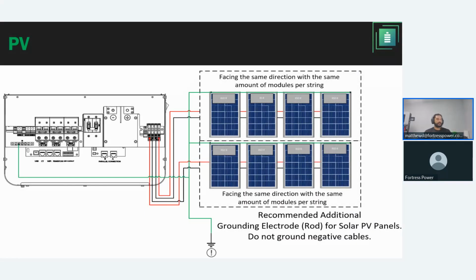Next is going to be the PV connection. As I mentioned before, we have two MPPTs, where we want to make sure that for the strings being connected, each module is facing the same direction. And if you are going to include rapid shutdown, if you're using a double rapid shutdown receiver, then you can put two modules into that receiver. If you're using a single module receiver, then you can install each module individually. Ground the modules, right? For ground mount installations, you don't need to install rapid shutdown.